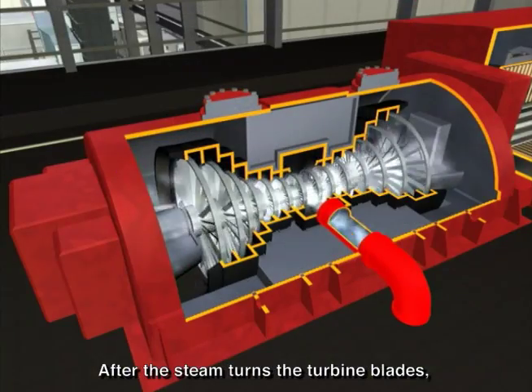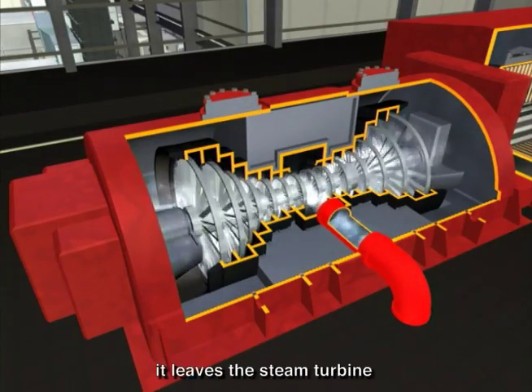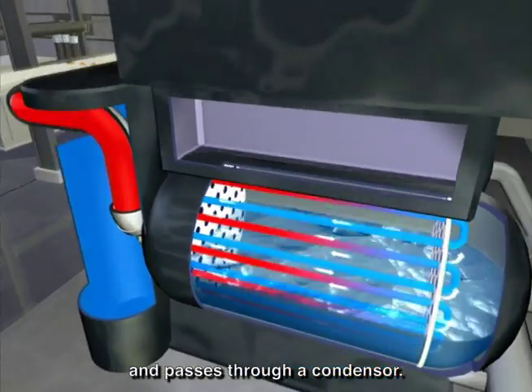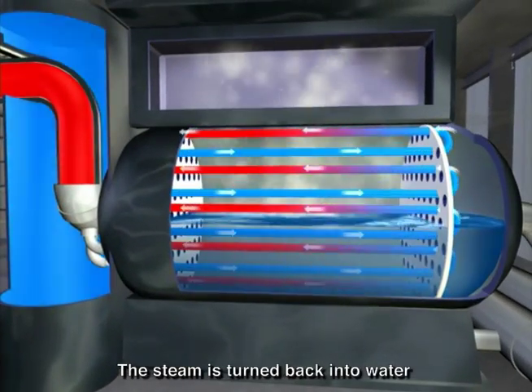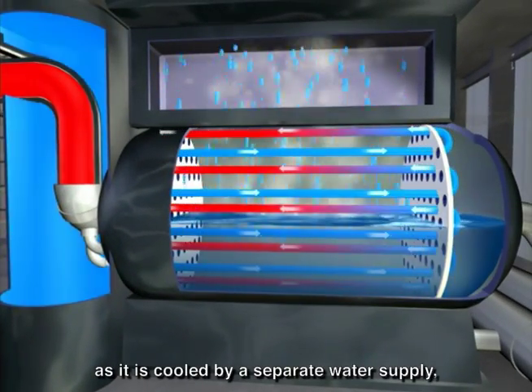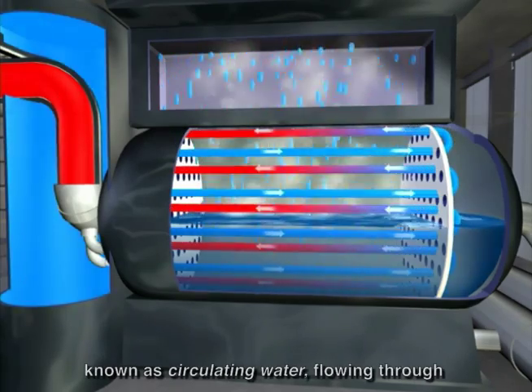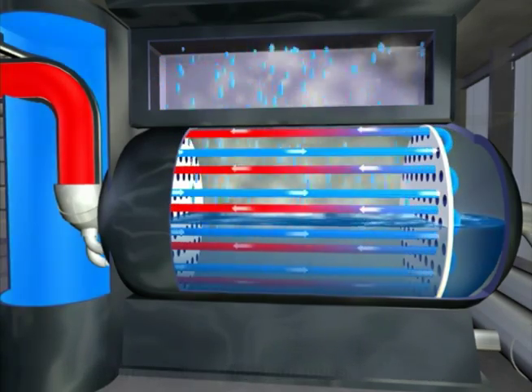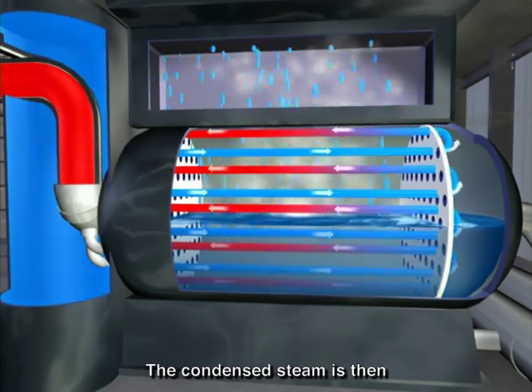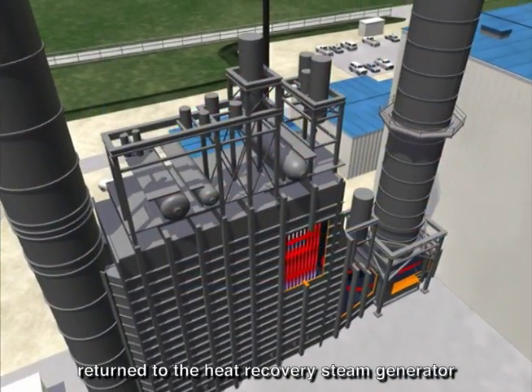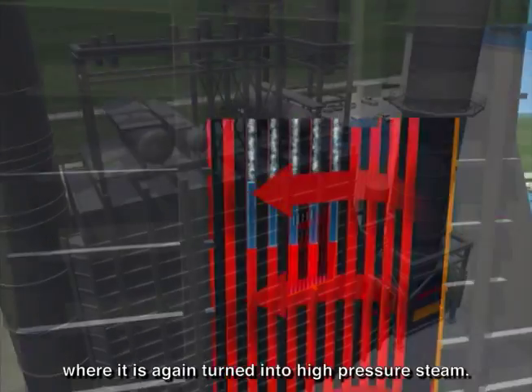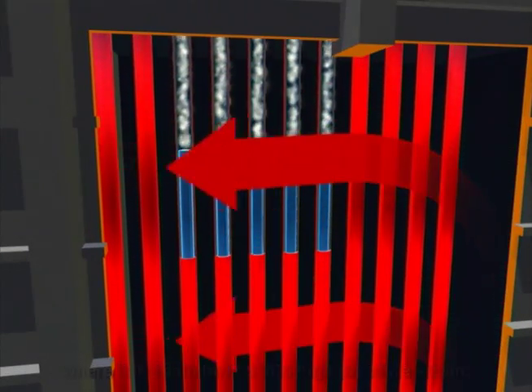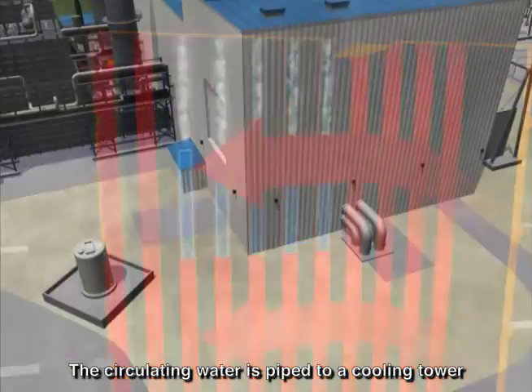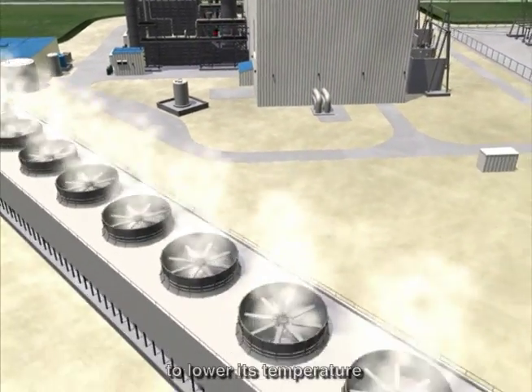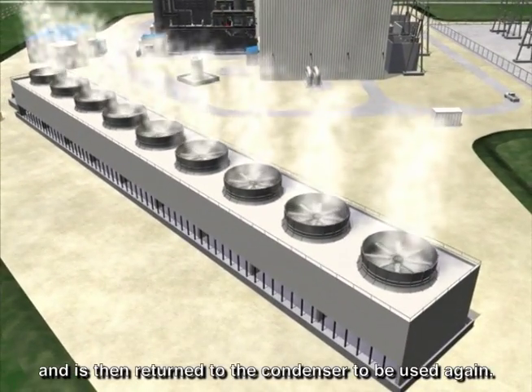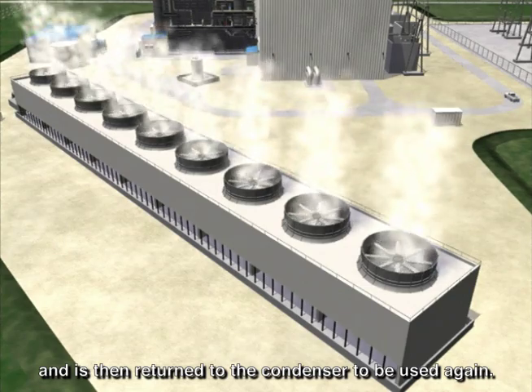After the steam turns the turbine blades, it leaves the steam turbine and passes through a condenser. The steam is turned back into water as it is cooled by a separate water supply, known as circulating water, flowing through the condenser tubes. The condensed steam is then returned to the heat recovery steam generator, where it is again turned into high-pressure steam. The circulating water is piped to a cooling tower to lower its temperature, and is then returned to the condenser to be used again.